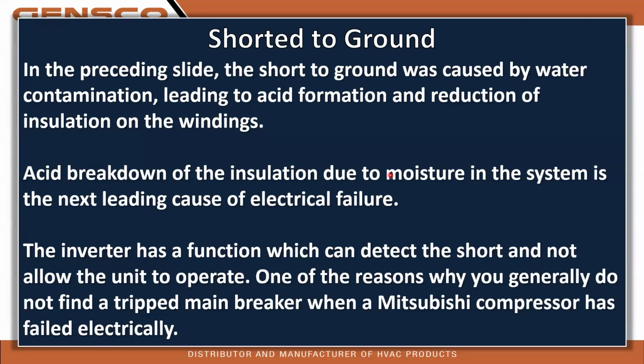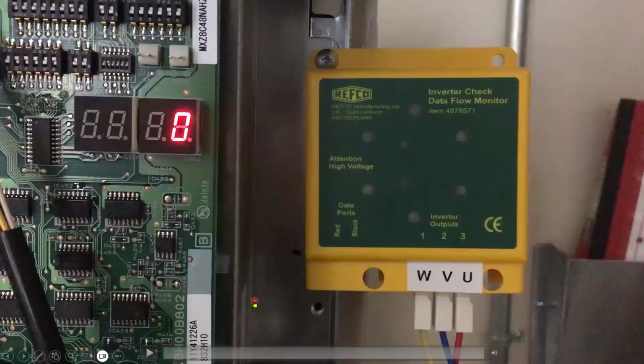The inverter has a function which can detect a short and not actually allow the unit to operate. This would be one of the reasons why you generally never find the breaker tripped in the power panel when a Mitsubishi compressor has failed electrically, because the inverter can see that and it will not let the unit run. So if you go to a unit, a house, a home, a business, and you start the unit and it doesn't even try to run, you just start getting an overamp error code, and the outdoor fan hasn't even tried to run. That is because the inverter has detected it.